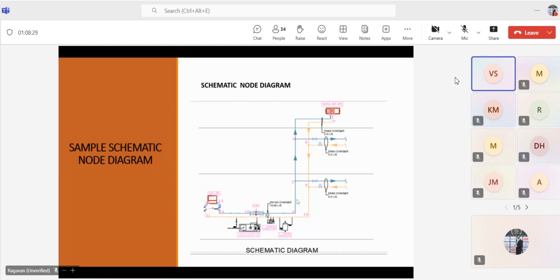At that time, what will happen? At the last, the furthest point, you will not get enough cooling. So people might think that during commissioning, it is not related to chilled water. They will think the issue is the coil or some other issue. But the issue is because of this one. That is why I am repeatedly saying the fittings are very important. You will definitely consider all the valves and the other components because they are the major parts, but mainly people miss the fittings. If we miss any fittings, it will definitely affect the efficiency of the chilled water system.